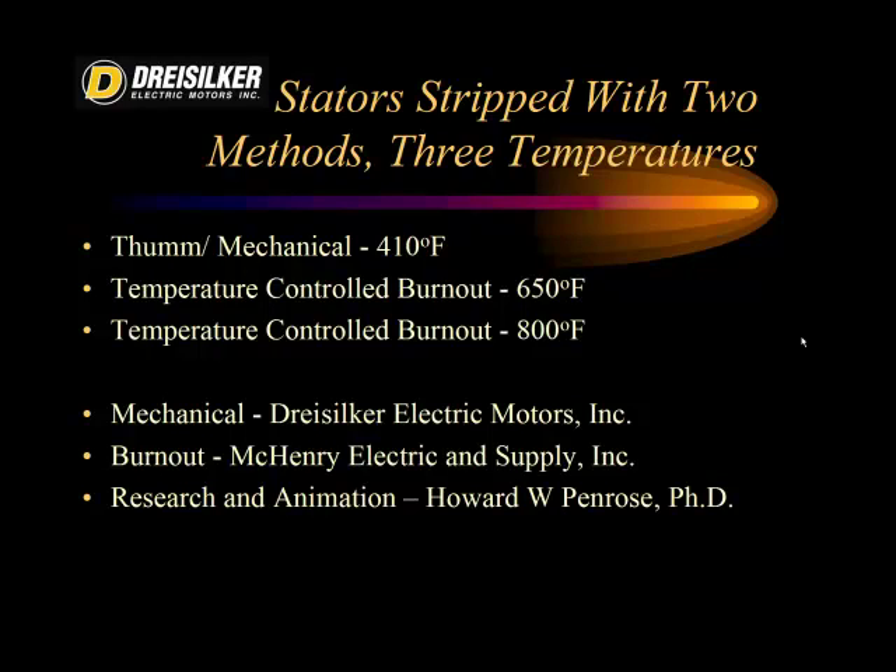We used a couple of different methods. The mechanical method — the Dreisilker approach — uses a maximum temperature of 410 degrees Fahrenheit. The temperature-controlled burnout oven with a water suppression system was tested at two temperatures: 650 degrees Fahrenheit and 800 degrees Fahrenheit. Those temperatures were the oven temperatures, whereas all studies actually indicate you should have a temperature sensor on the stator core as the maximum reference. In reality, people set burnout oven temperatures to 650 or 750 without a temperature sensor, and we found cases where people turned off their water suppression systems to strip motors much faster.